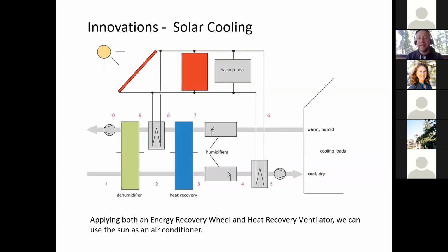So you're going to cool it down, but it's really moist. And then it's going to go through a heat recovery section. So this is just the sensible load. That now cold air is going to, as it moves through the heat exchanger, warm up, and simultaneously on that bottom line, it's going to be cooling that airstream down. So as we go back up to the top, as I go from 7 to 8, the air has warmed back up. So now it's sort of neutral air, pretty moist.